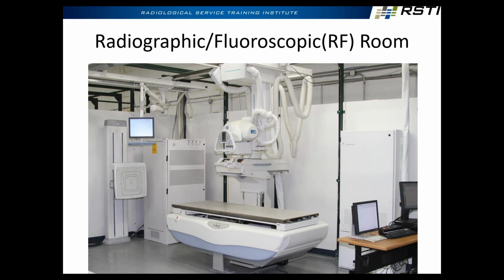So what you'll see here is there is an over-table X-ray tube. Why do you think they call it an over-table tube? It's over the table. Well, guess what? There's an under-table tube. Guess where it is? Inside the table. So the point is, an R&F room has 2 X-ray tubes and 1 generator, so you can only use 1 at a time. The over-table tube is going to be, well, exclusively used for what type of exams? Still radiographic shots, 2D. The under-table tube is going to be used for fluoroscopy, video, moving, motion, things like that.